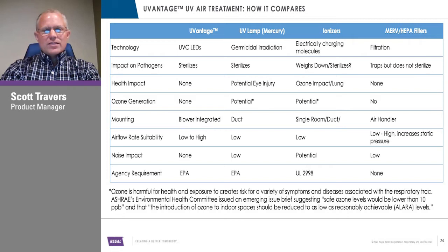UVC LED technology is efficient, low profile, and has a longer life — potentially upwards of 10 years. Not really as sensitive to temperature, whether it's on the downside of the evaporator coil or in the warm side. We really feel like it's the technology of the future. It's a very nice compact design and works very well compared to the others.